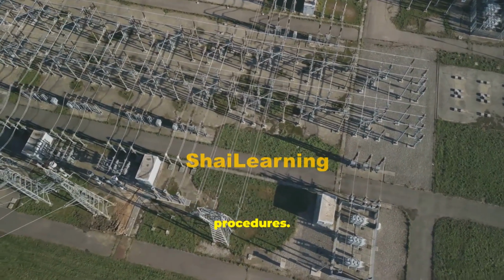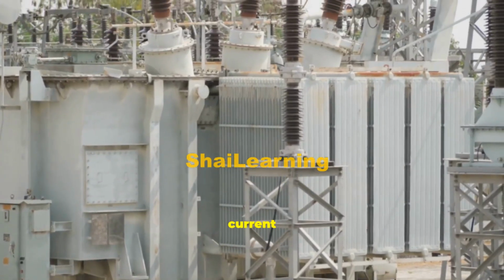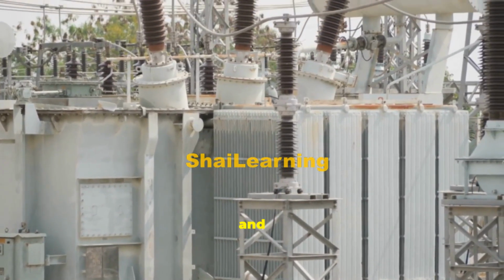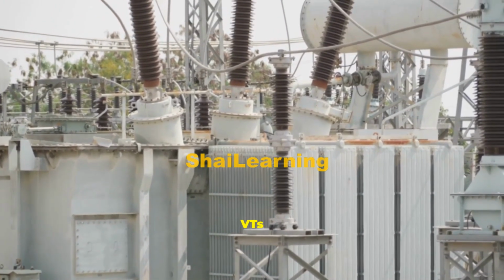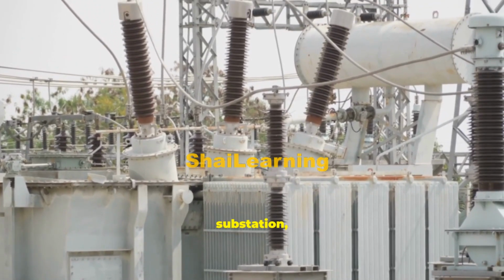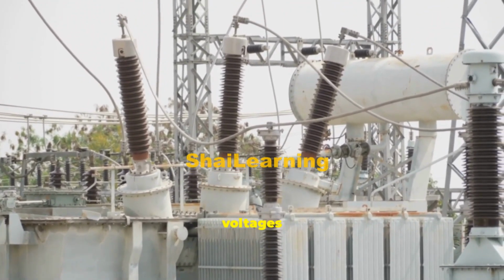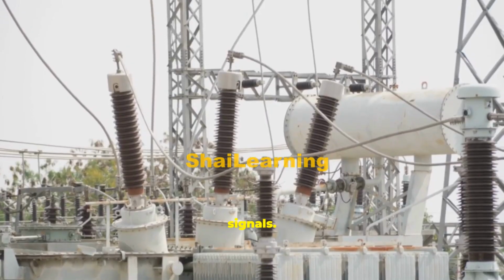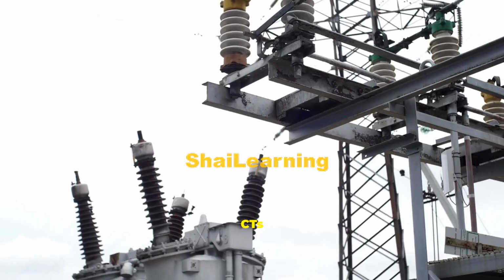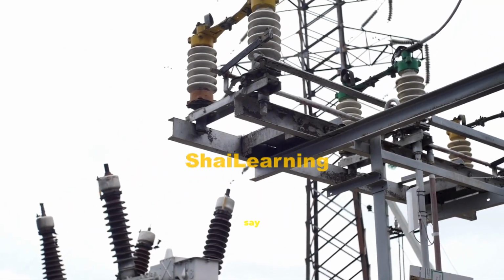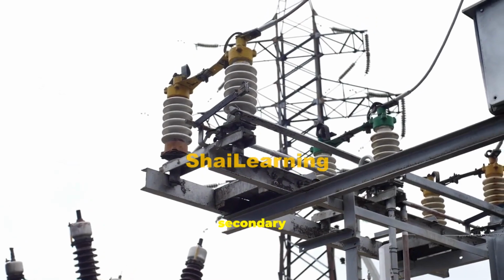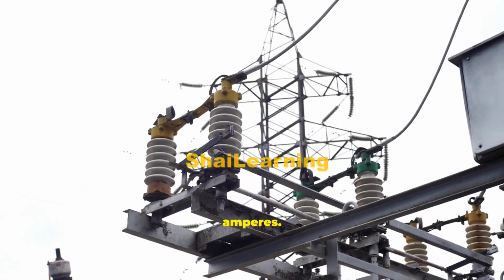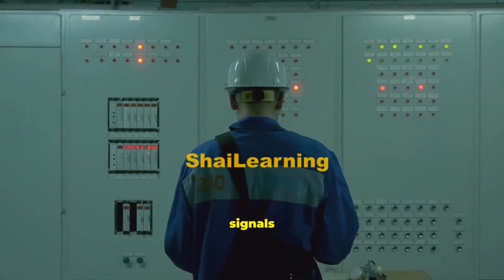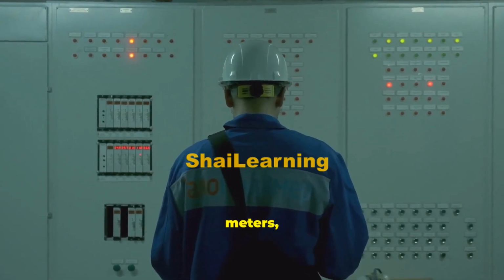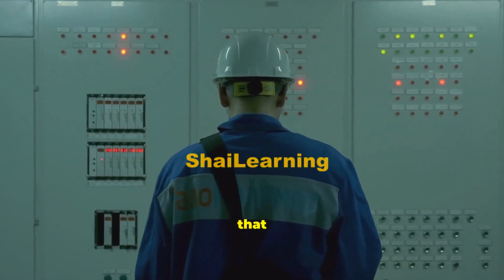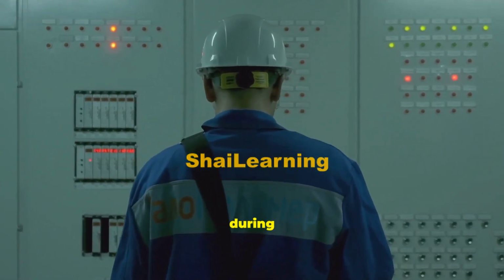procedures. Instrument transformers, current transformers, CTs, and voltage transformers, VTs, are the senses of the substation, scaling high currents and voltages to safe signals. For instance, CTs can step down high primary currents, say 4,000 amperes, to secondary currents of 1 or 5 amperes. Those small, accurate signals feed the brains, relays, meters, and communication equipment that monitor the grid and operate breakers during a fault.